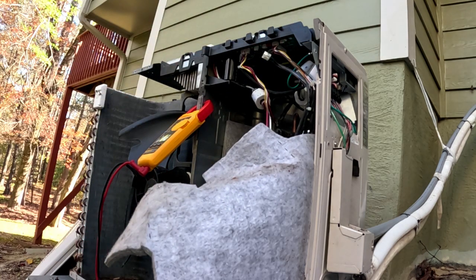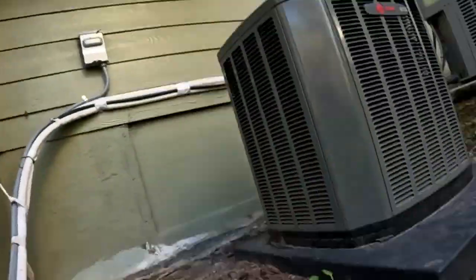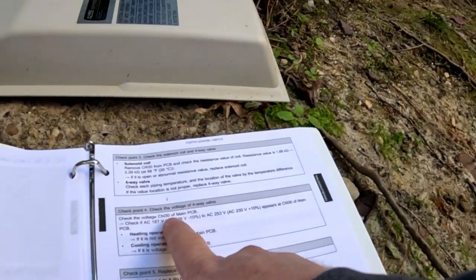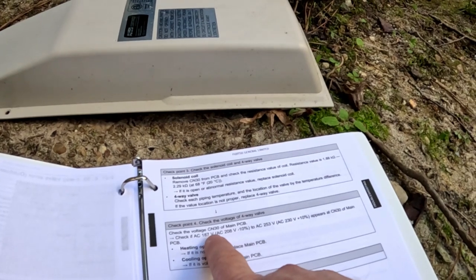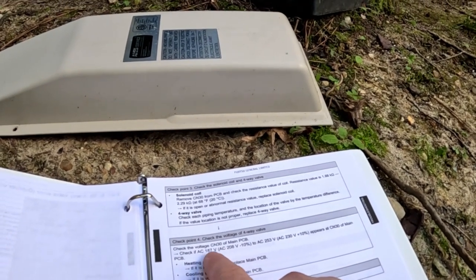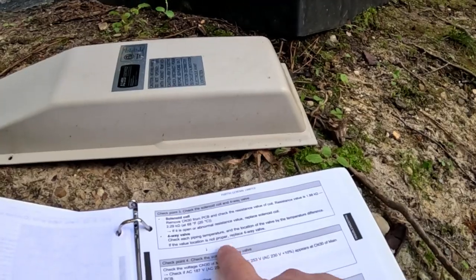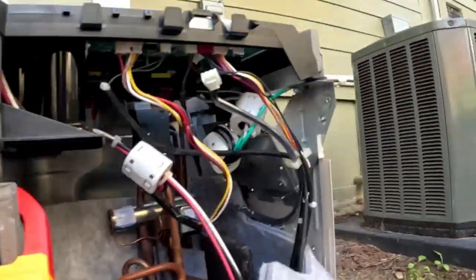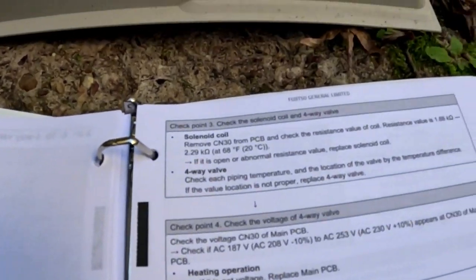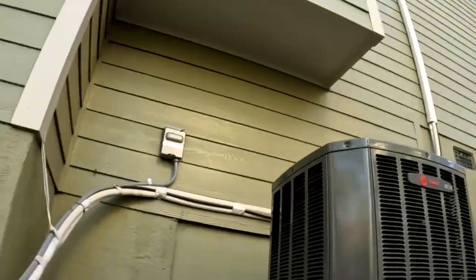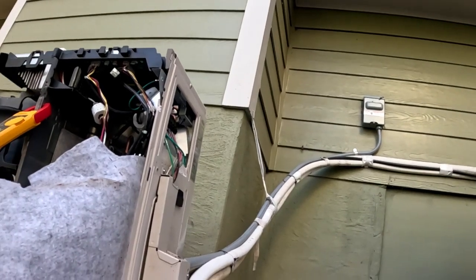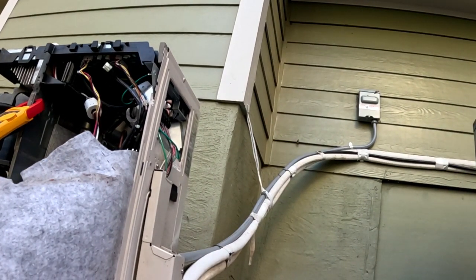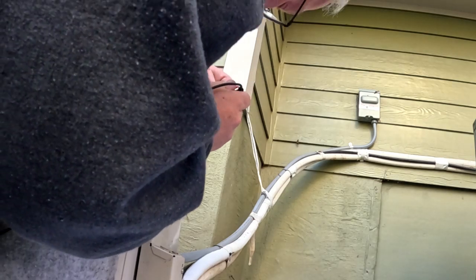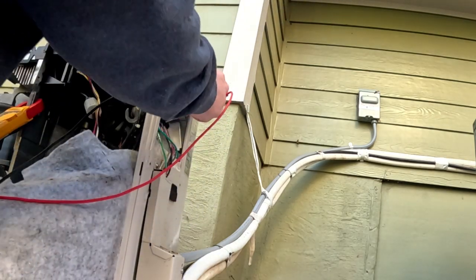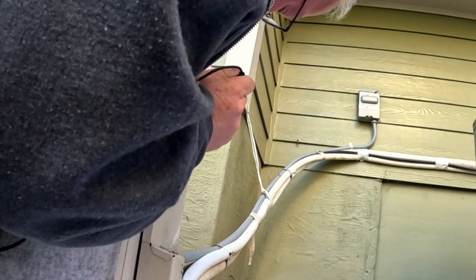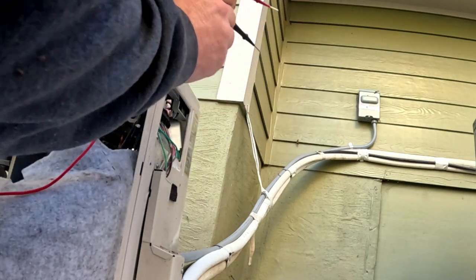Not getting anything, and that's the confusing part, because it tells you check the voltage and you're looking for 187 volts or 253 volts, but it's odd that it would say at the same terminal that the solenoid is on, because I'm pretty sure that's not going to be a 100 and some volt terminal. We do have 248 going to the unit and 248 going back inside.